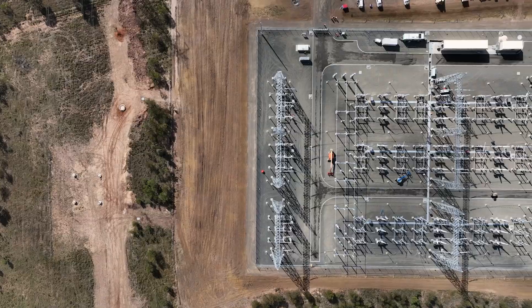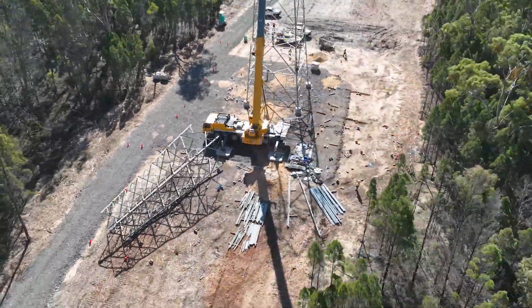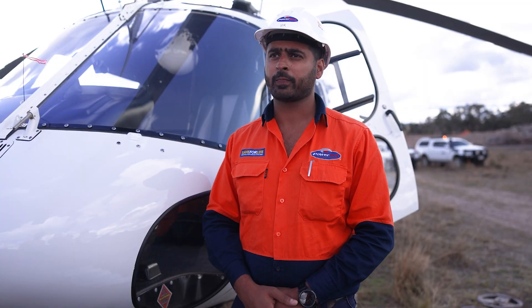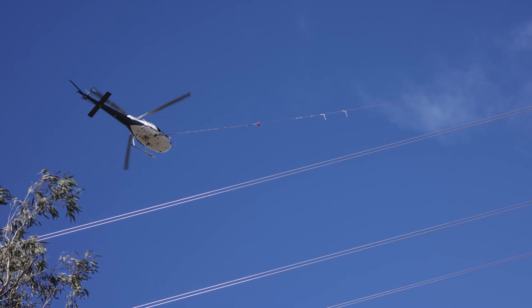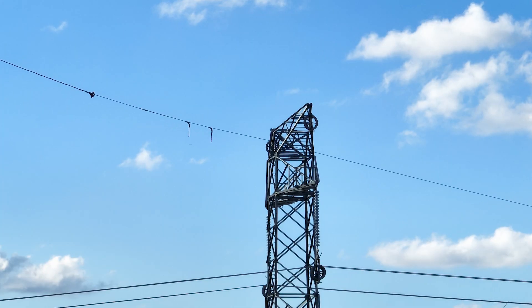We've completed all civil works and all foundation works. We've completed 95% of tower assembly and erection, and we're just over halfway with our stringing. We use helicopters to pull draw wire or conductor from the ground at brake and winch sites through the towers — it's quite an exciting thing to see happen.